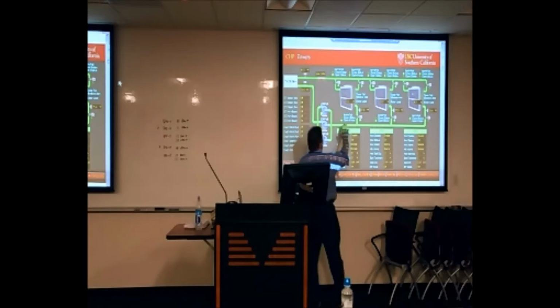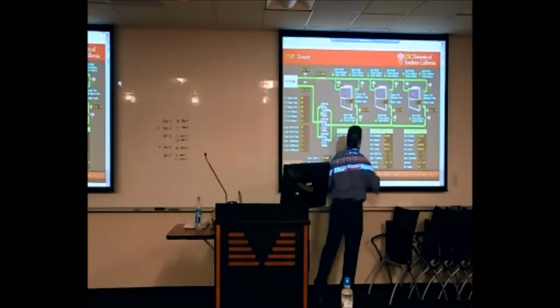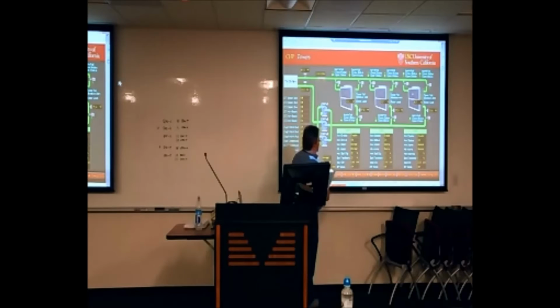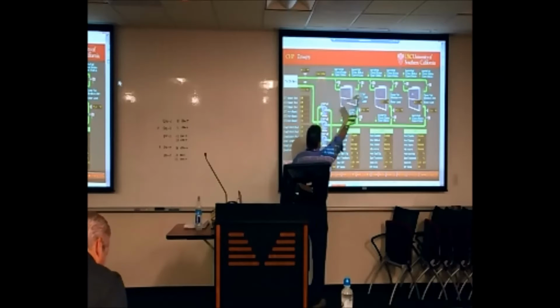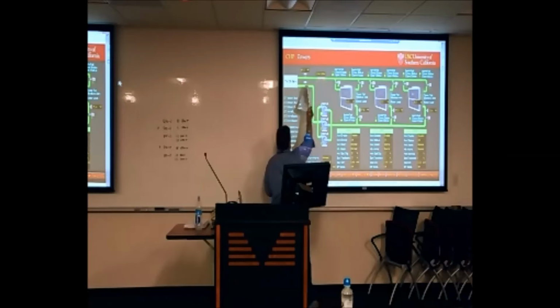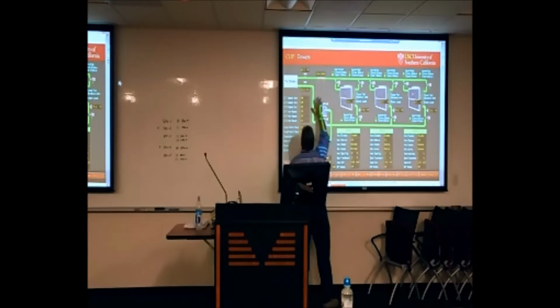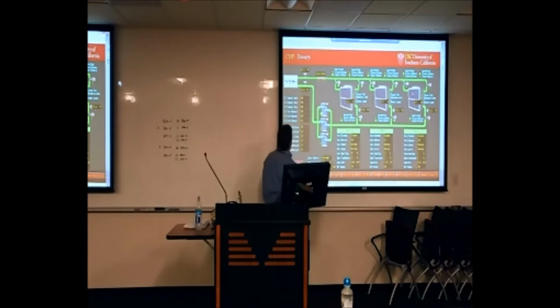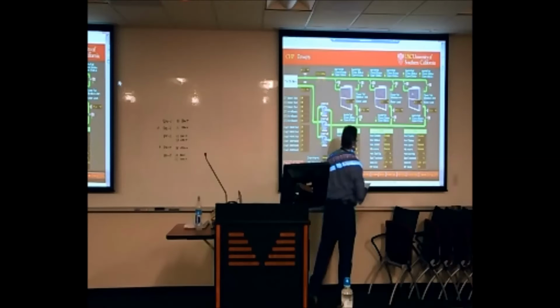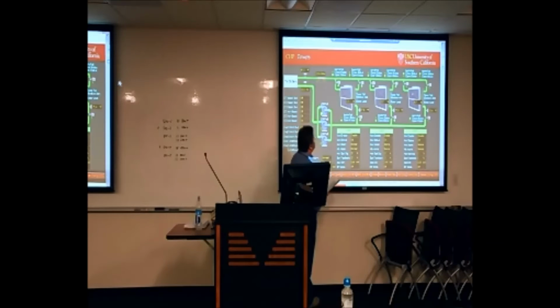And then each tower also has a leaving temperature sensor underneath the tower. That's the water leaving the cell. So we have a reading of the discharge from each one of the towers, and we have a common supply coming from the central plant to that header that feeds all the towers. So that temperature is the same for each of the towers. And then, of course, the water that comes out hits the pump, and then this is our controlling sensor right here. That's the condenser water supply temperature back to the chiller, and this is what we're controlling off of right here, that common sensor. But again, there is that indication of how each tower is performing right there with its individual sensors.